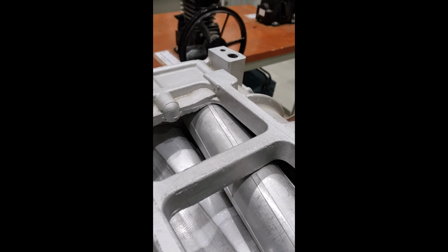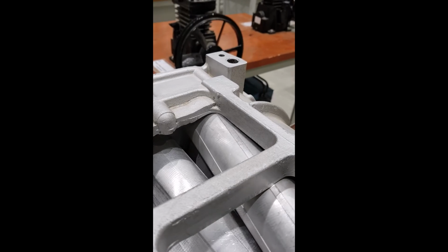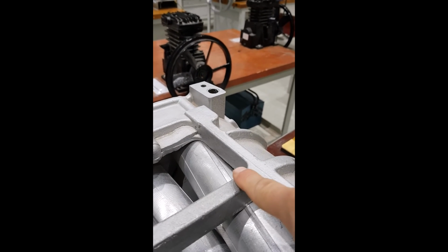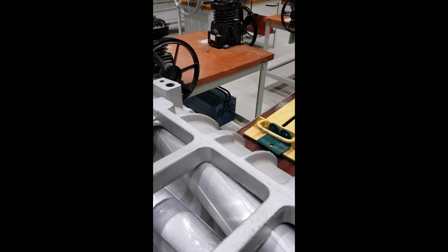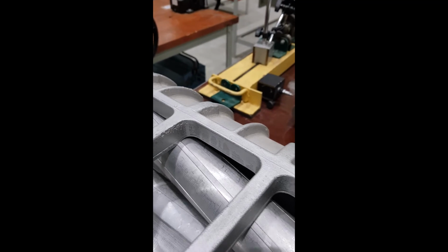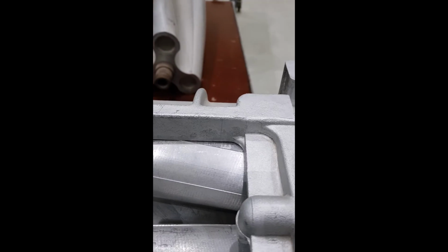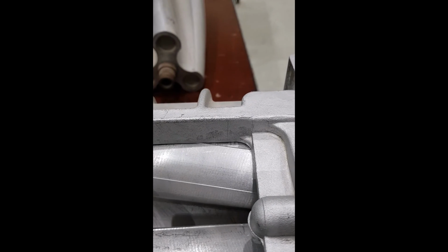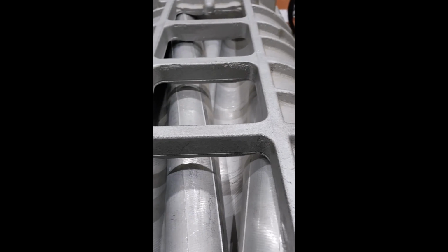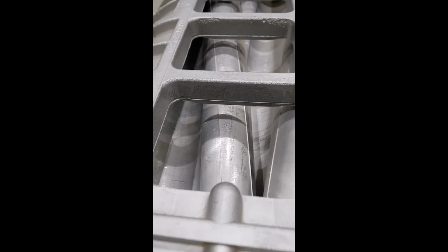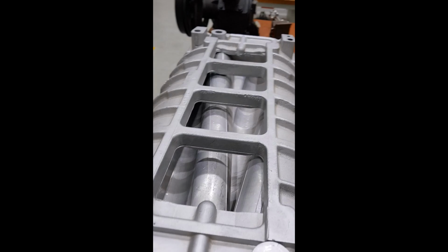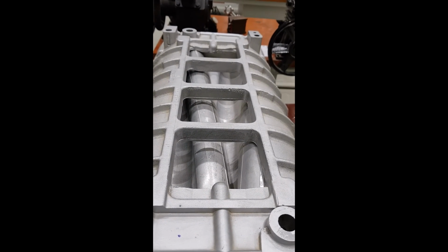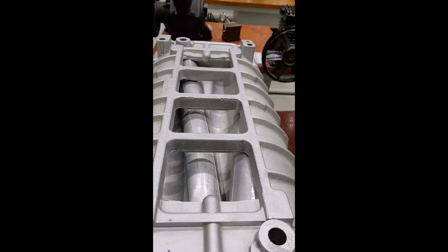If I want to take casing and rotor, I can take it in this area over here, or I can rotate this one a little bit and take the reading somewhere over here, or maybe in this area, the smallest gap. Similarly, in between the rotors, I can take it at any place along the lobes. This compressor is a rotary compressor, which falls under the positive displacement compressors.